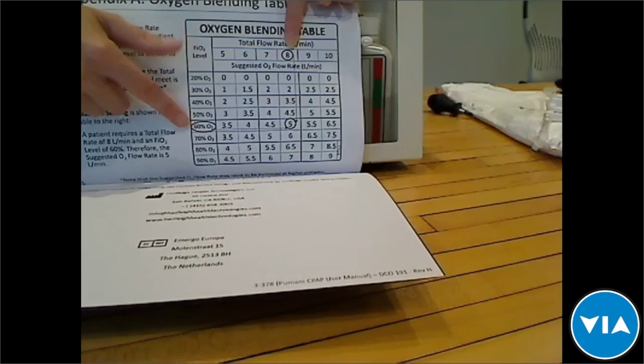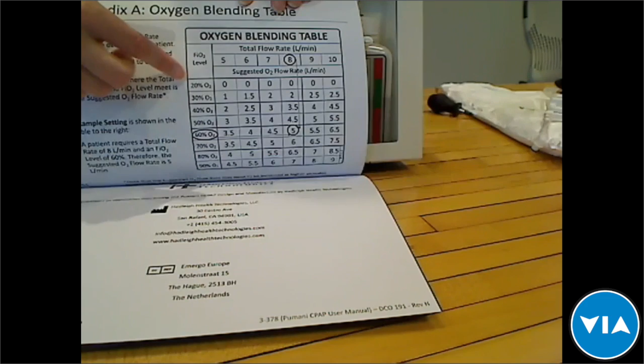And where these two values meet is 5 liters, and that is what your oxygen flow would be. So I've set my total flow to 8 and my oxygen flow to 5, and that will give me 60% oxygen in the baby's airway. And so you can do a variety of different settings to deliver different percentages of oxygen to the baby.